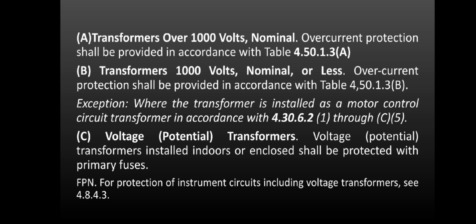A. Transformers over 1000 volts nominal: overcurrent protection shall be provided in accordance with Table 4.50.1.3 A. B. Transformers 1000 volts nominal or less: overcurrent protection shall be provided in accordance with Table 4.50.1.3 B. Exception: when the transformer is installed as a motor control circuit transformer in accordance with 4.30.6.2 (1) through (C)(5). C. Voltage potential transformer. Voltage potential transformers installed indoors or enclosed shall be protected with primary fuses.